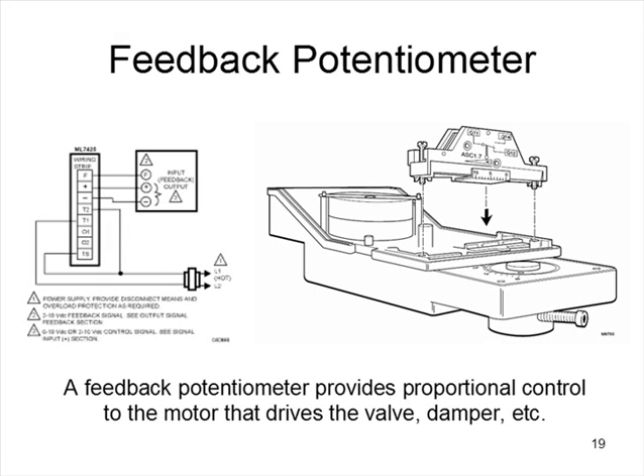You demand 68 degrees and the room dropped to 50. All right, open the valve most of the way. Okay, the room is demanding 68 and you dropped to 65. Well, open the valve about a quarter of the way. You know, that kind of thing. That way you don't overheat. All right, you maintain a simple efficiency just by regulating, just like a TXV valve does.